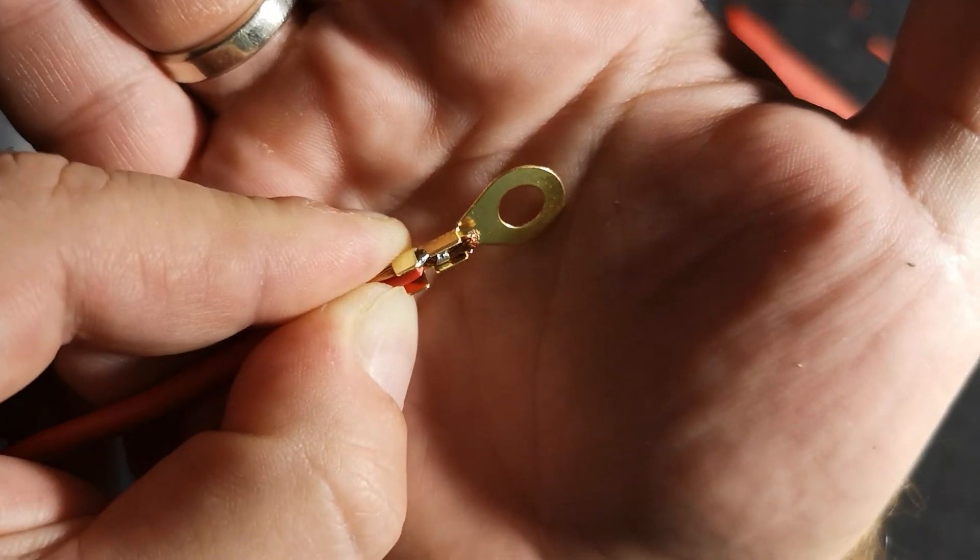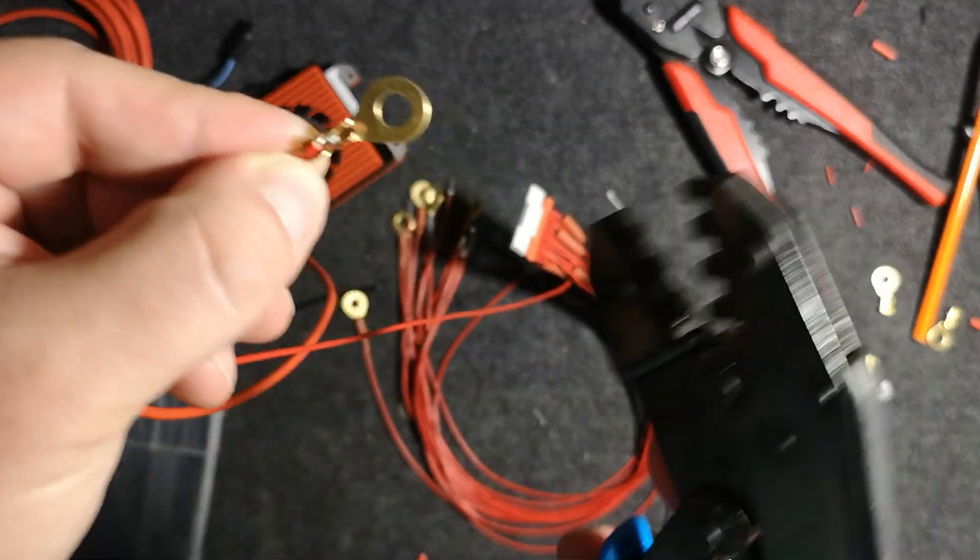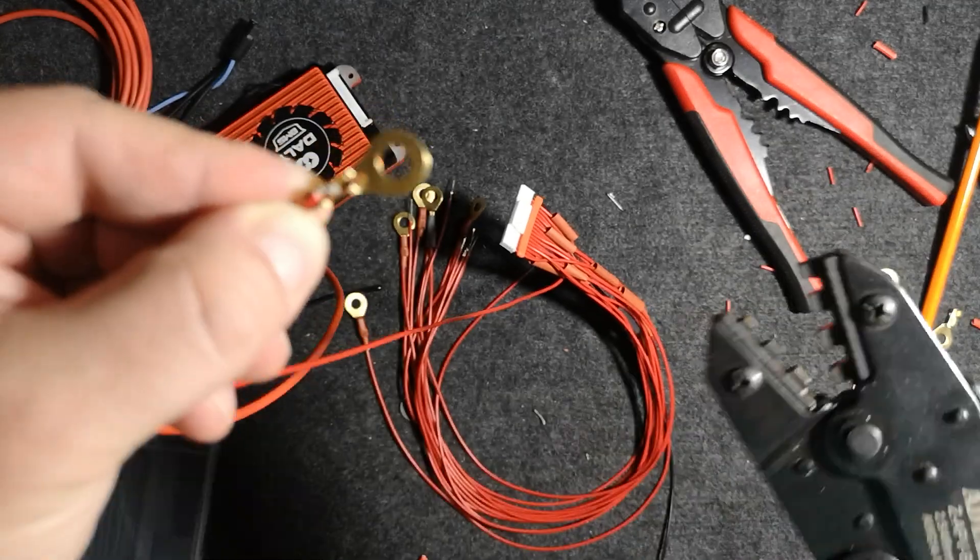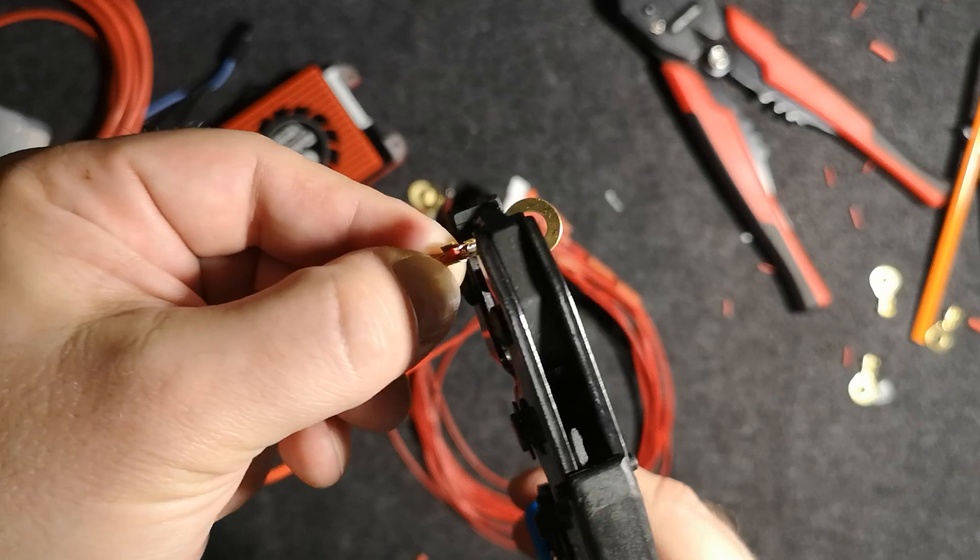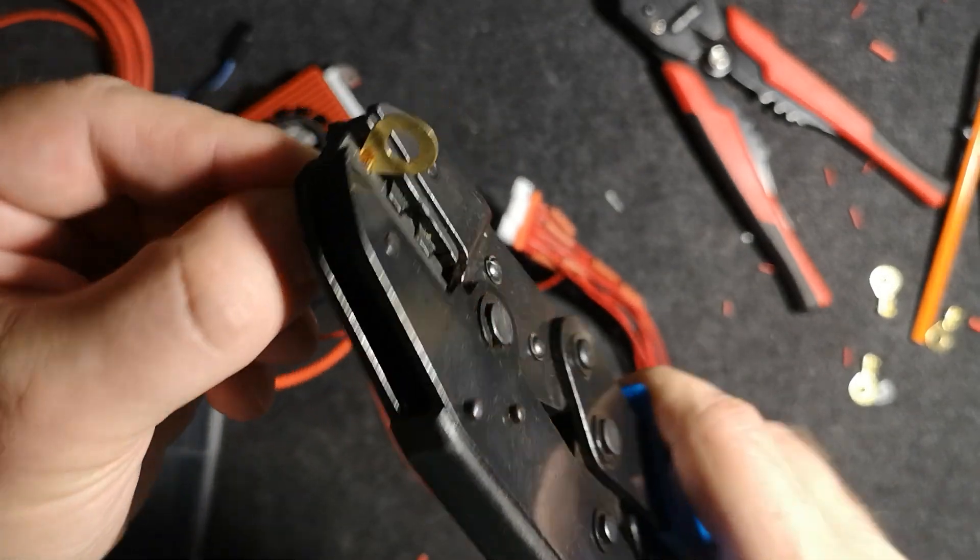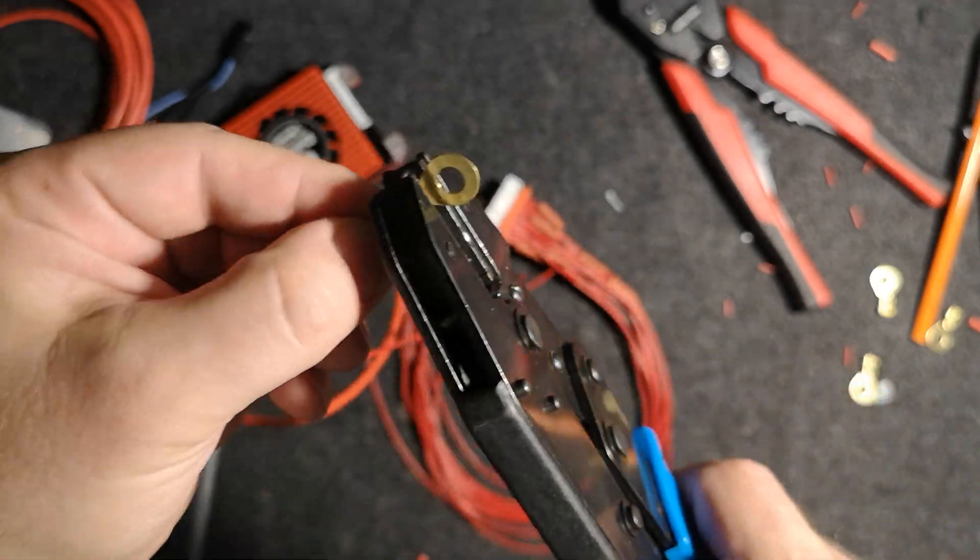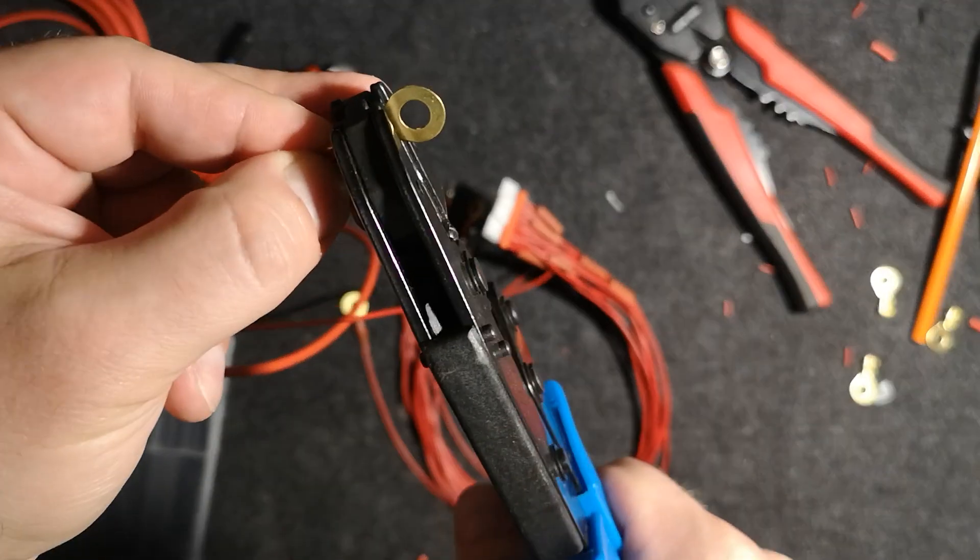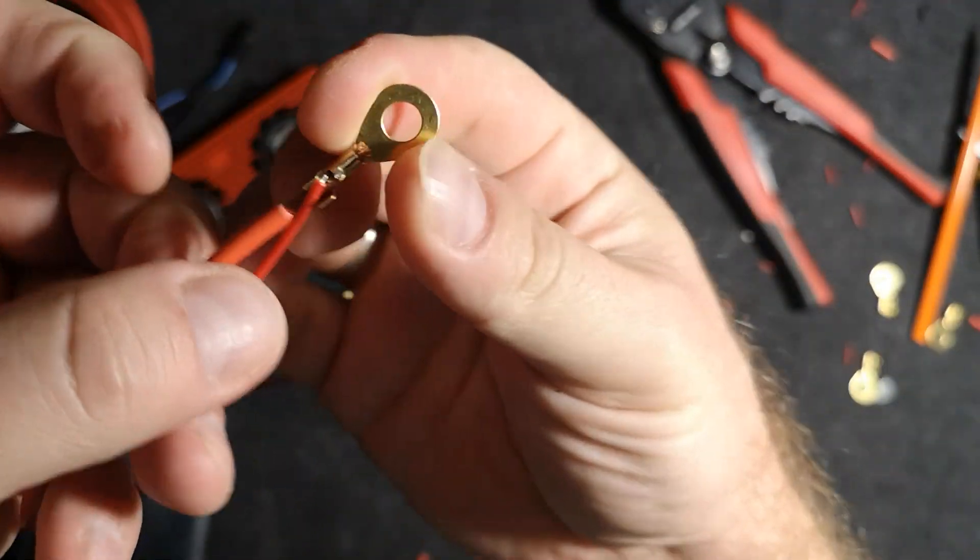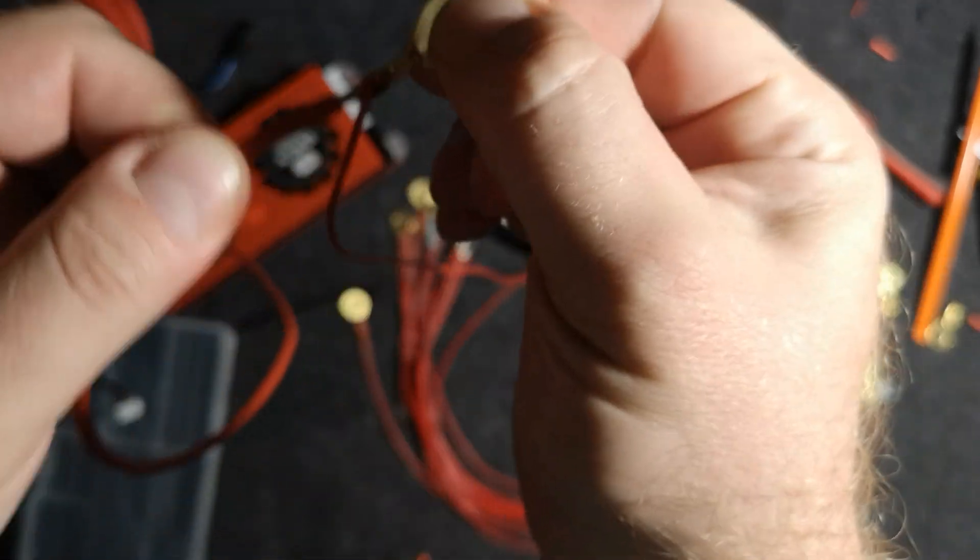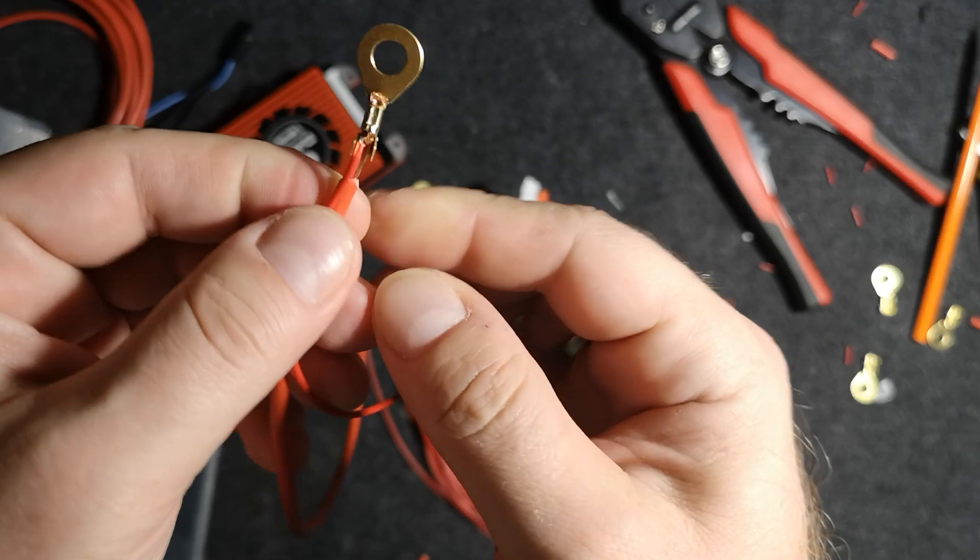All right, now it's in. Now I'm taking the crimping pliers. I will be crimping only this first part using 2.5 because this is dedicated size for this ring terminal. So I'm putting it in here and squeezing. So now as you can see we have nice crimp, but try to remove this cable. This cable really nicely holds.